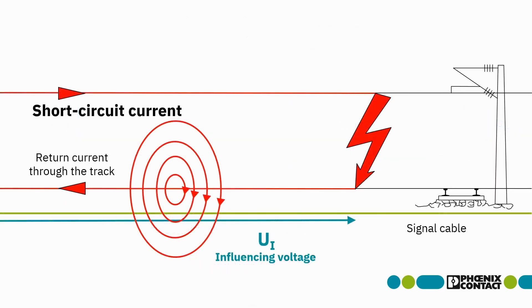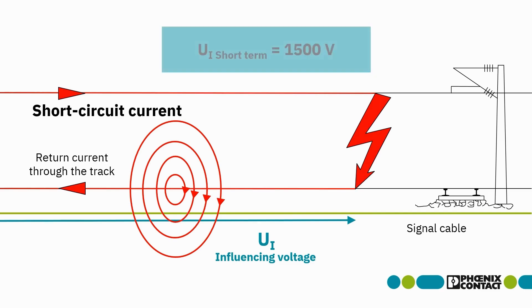In the special case of a short circuit, for example due to a crack in the overhead line, the significantly higher short circuit current also induces a significantly higher voltage. This so-called short-term influencing voltage is defined as a maximum of 1500 Volt.